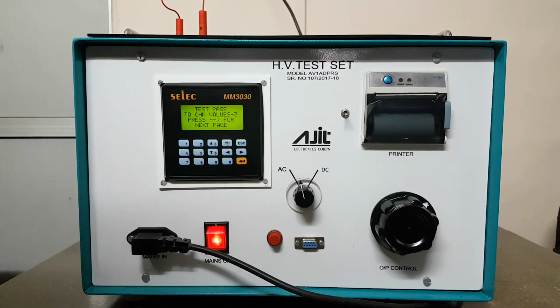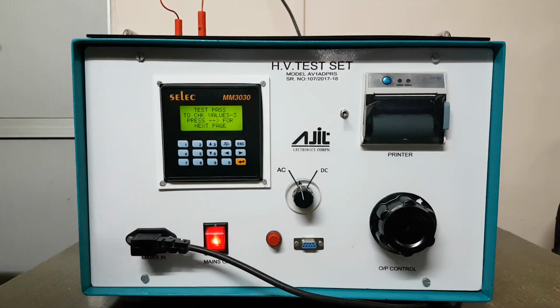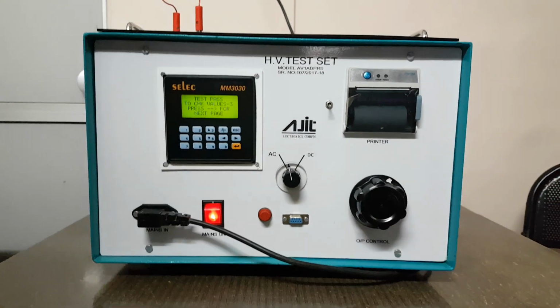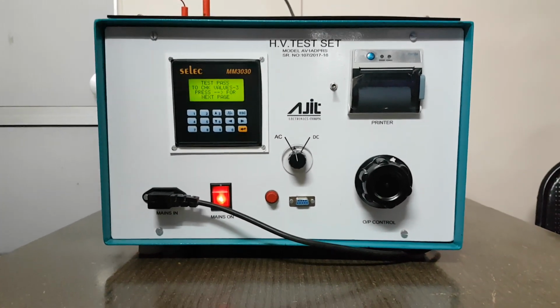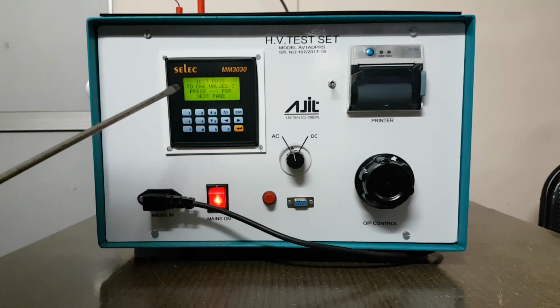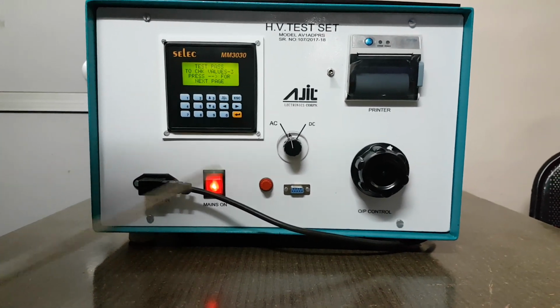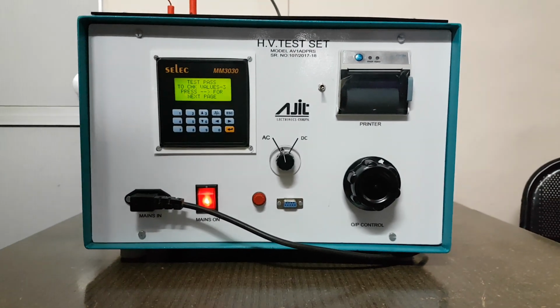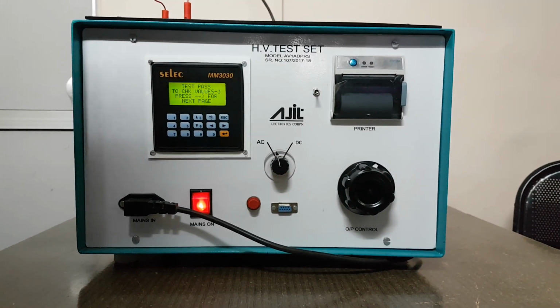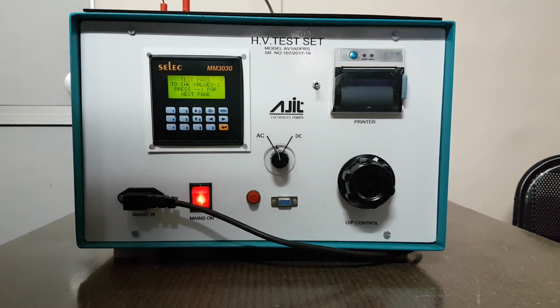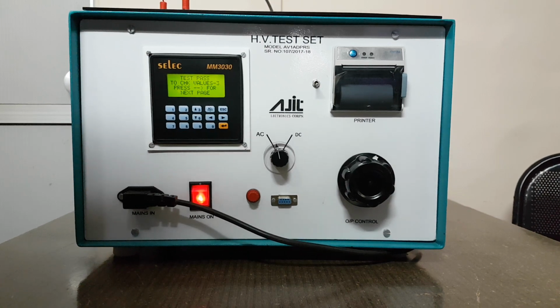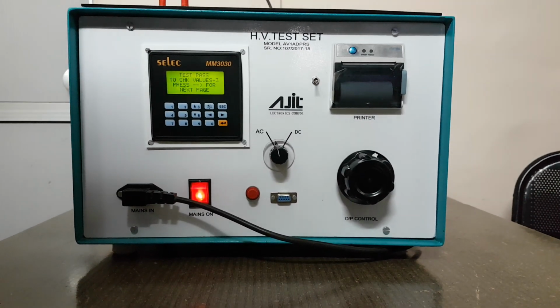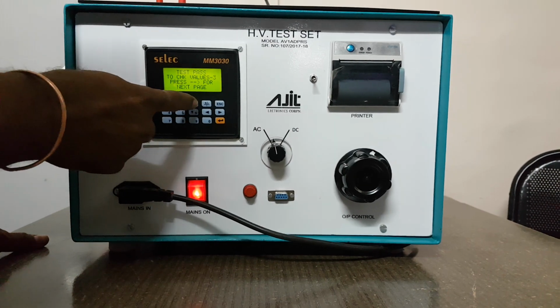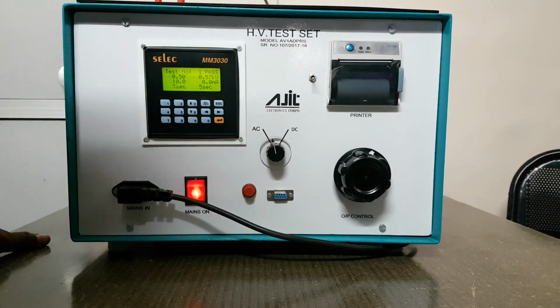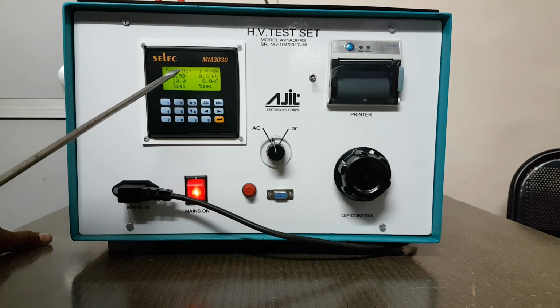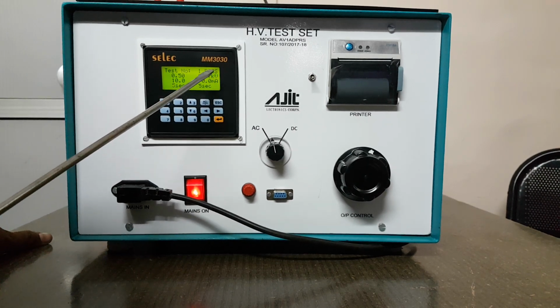Now the test is completed and the test has passed because there was no overcurrent tripping during the test. To check the values of the test result, press right arrow, then key number 3. Press right arrow for the next page. So let's see with key 3 the test number. The test was passed.